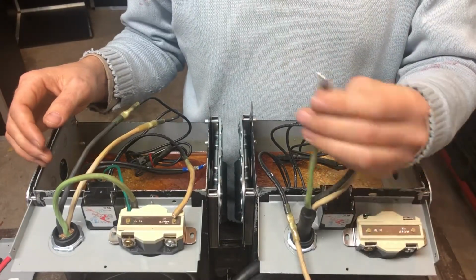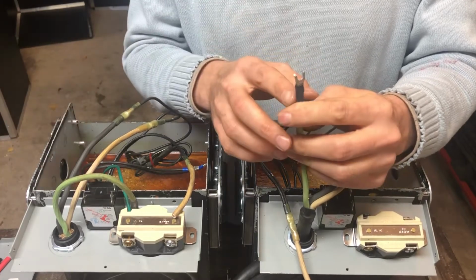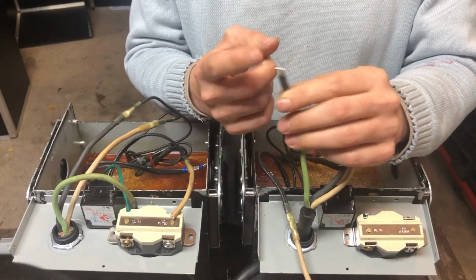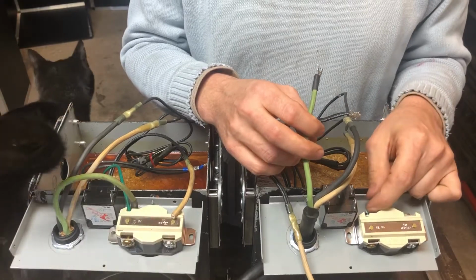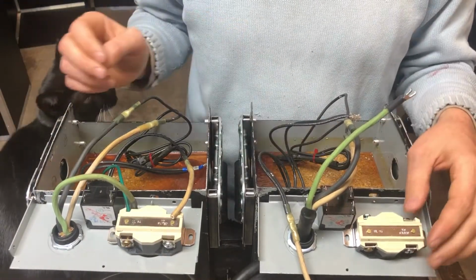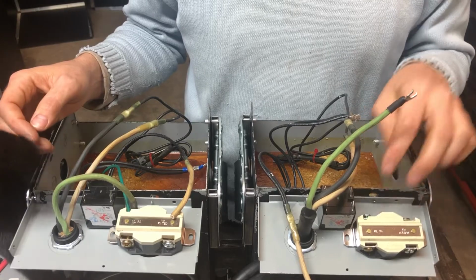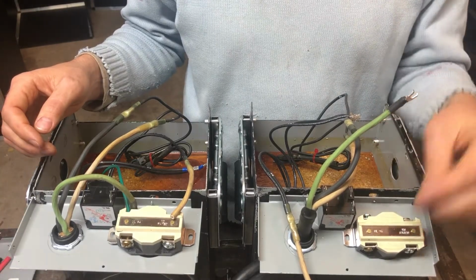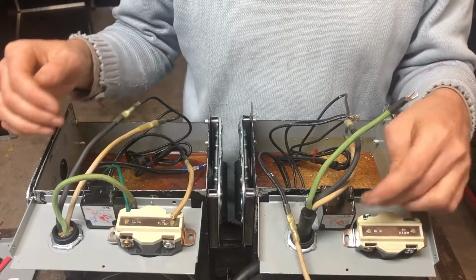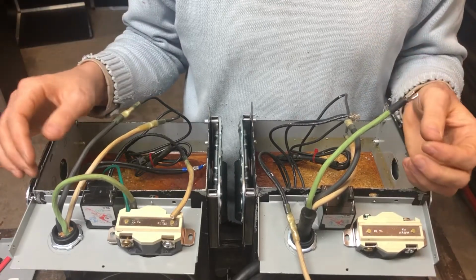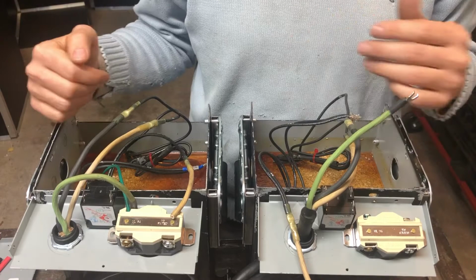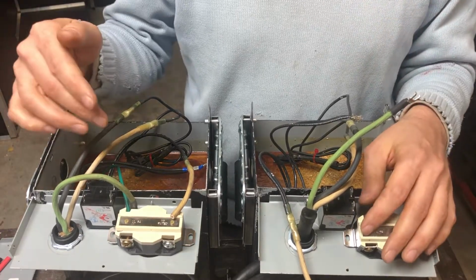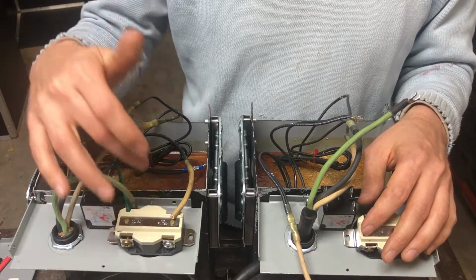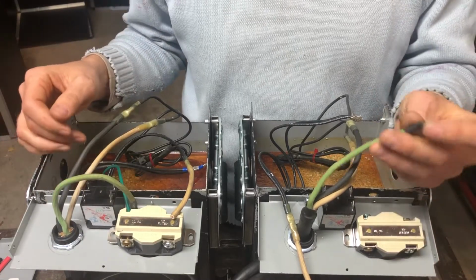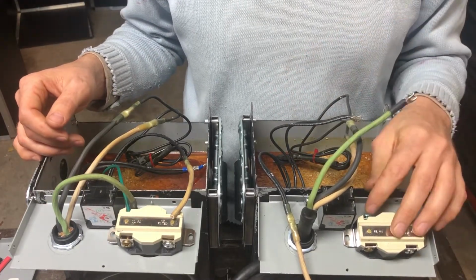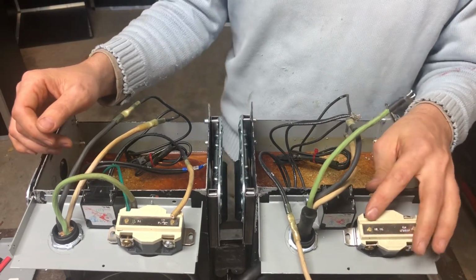So I have my incoming ground, and I have a spade with those tabs on it that I like, and I'm going to hook that on the screw. But these devices are also taking under-tab wiring, so you can put the stripped wire under the tab without any connectors. But because I have the ground of the transformer and the ground of the device, I'm gonna do the ground of the transformer under the tab, and then use this hooked eye on top of the screw to make the ground connection.